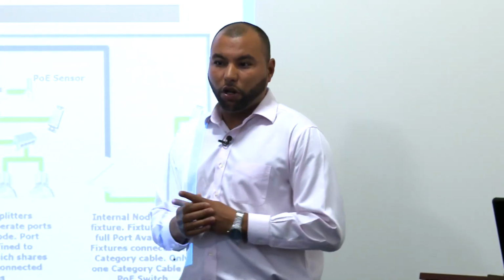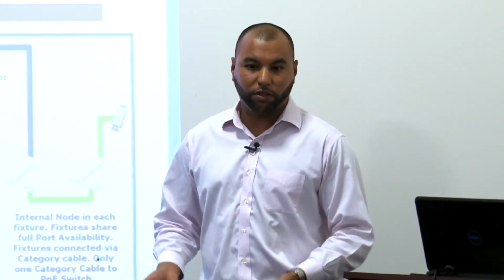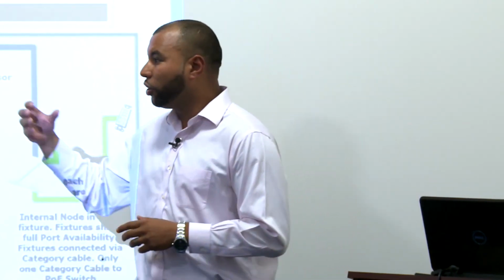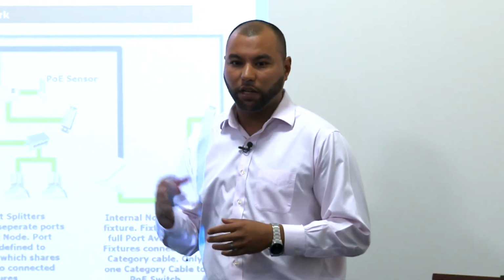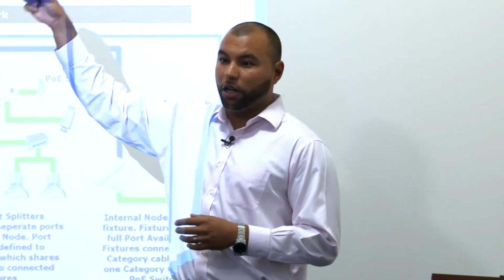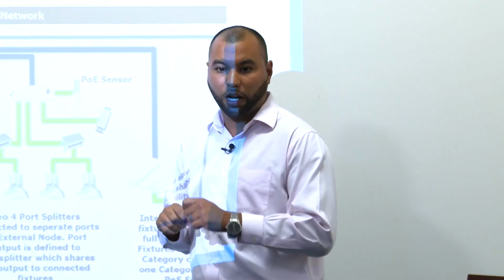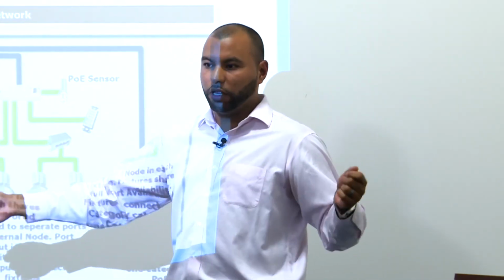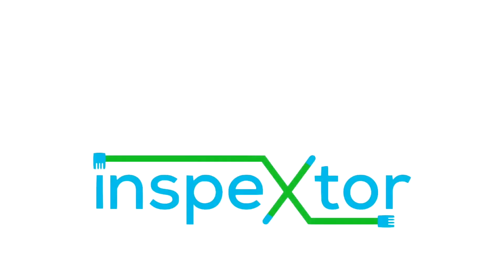There's two ways you can install a sensor. It either comes with the fixture, you don't have to do anything. It's already in the fixture, you just plug the fixture in and it recognizes that. Or you physically have to mount it, and once we go to the showroom, you'll be able to see what it looks like. It goes into a 1-inch hole, so you drill a 1-inch hole, you put it in, and then you plug an RJ45 cable into it. Some of our products actually have a 10-foot lead of an RJ45 today that you'll be able to pull to your node and plug into the control side.